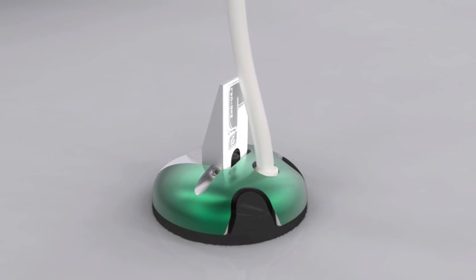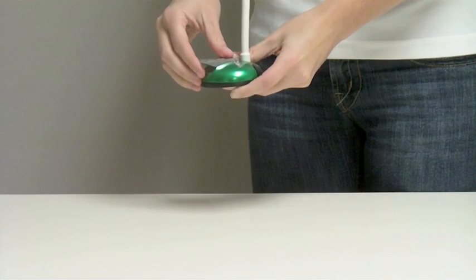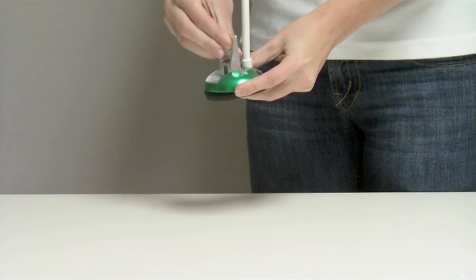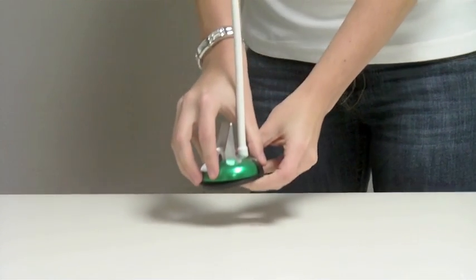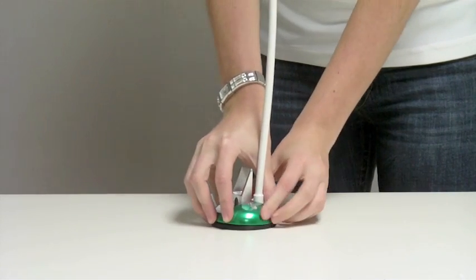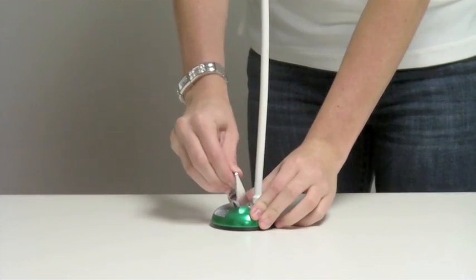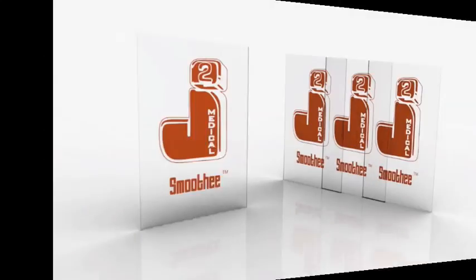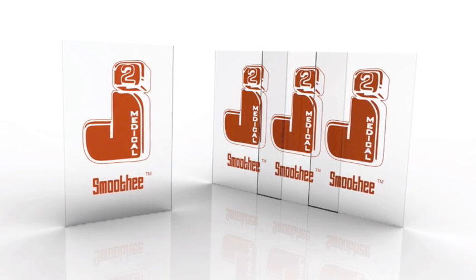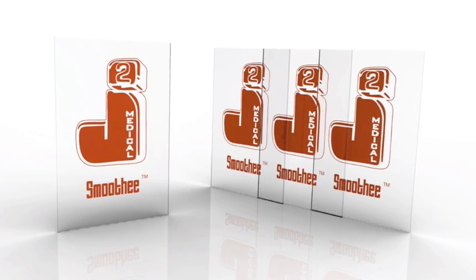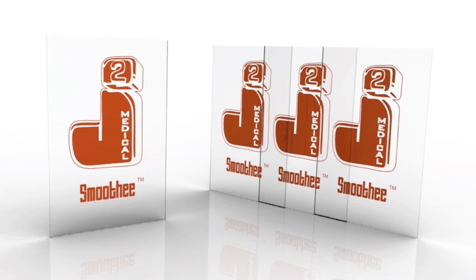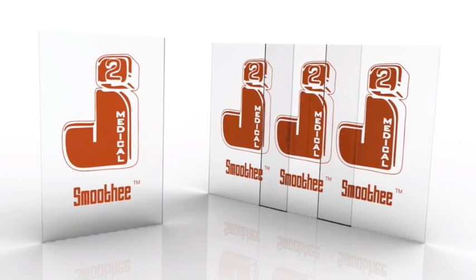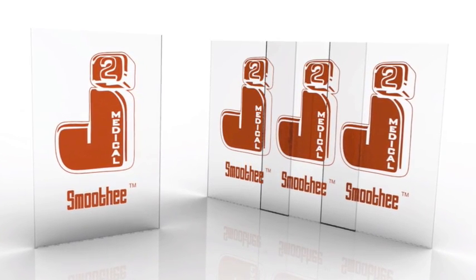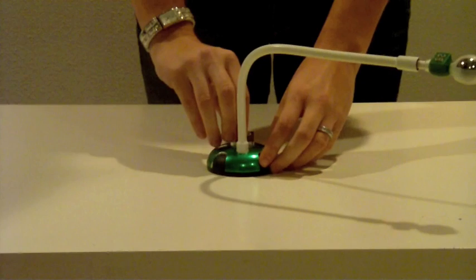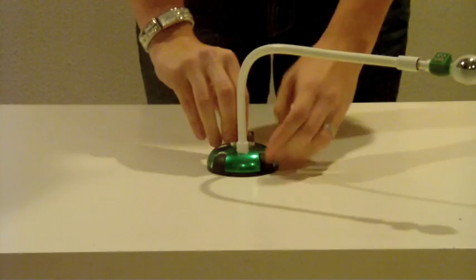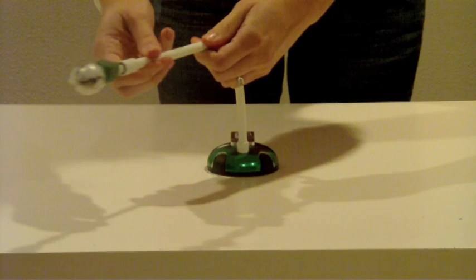To attach the Akucal, make sure the suction cup lever is released. This can be done by simply lifting the lever up. Firmly press the base of the Akucal onto any flat, smooth surface. While firmly pressing, push the lever to the horizontal position. If your table or upright bucky surface is a textured material, please contact us about the Smoothee surface strips. The Smoothee surface strips make any non-smooth surface suctionable. Once the Akucal is attached, position the sphere by gently bending the flexible arm into place.